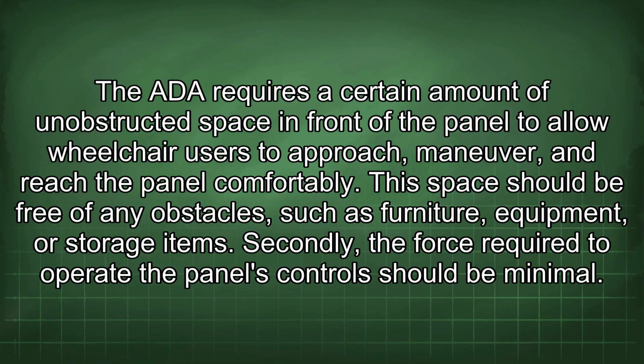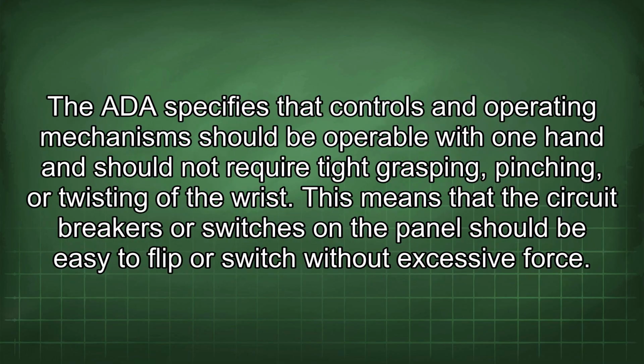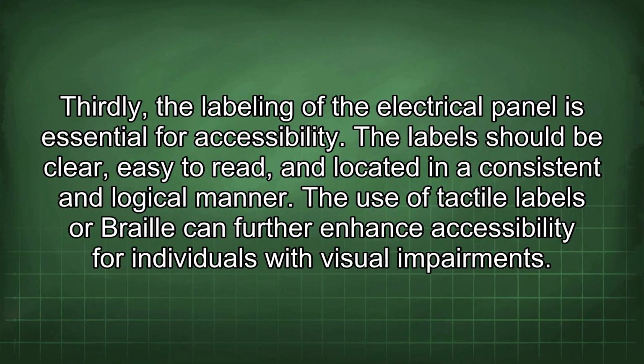Secondly, the force required to operate the panel's controls should be minimal. The ADA specifies that controls and operating mechanisms should be operable with one hand and should not require tight grasping, pinching, or twisting of the wrist. This means circuit breakers or switches on the panel should be easy to flip without excessive force. Thirdly, the labeling of the electrical panel is essential for accessibility.